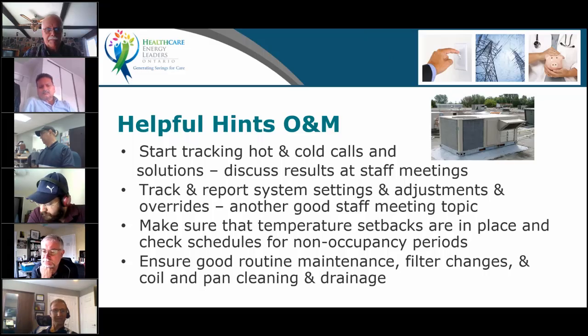Thank you. The other hint that I want to give, and that's a myth I sometimes hear, is about temperature setbacks. If you've got an electrically heated building and you do a temperature setback in a section that is not obviously 24/7 occupation, so it has to be unoccupied, you will be able to save. People say, hey, it doesn't save. Setback always saves energy. It can hurt you on demand, and you will pay more at the end of the month, but it saves energy.